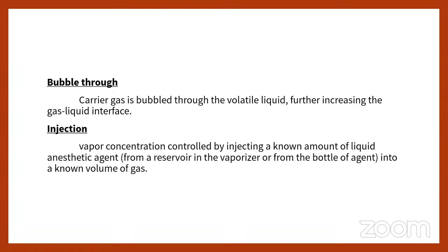Bubble through: in this, the fresh gas is passed through the liquid agent, and as it is air in a liquid, it causes bubble formation. These bubbles come out of the liquid and enter the vaporizing chamber. When they reach the vaporizing chamber, it is already coated with the anesthetic agent. So these bubbles burst and form an anesthetic and fresh gas mixture. This mixture passes through the outlet and is delivered to the patient.